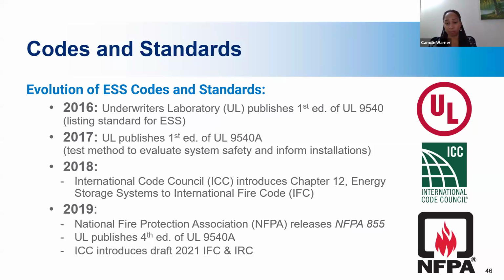It's a certification. In 2017, UL 9540A was developed. This is not a certification, it's a destructive test that provides data to review to make sure you're making informed siting decisions. UL 9540A is not a pass or fail test; it simply tells you how the system will behave under a stressful situation. This is why peer review is crucial, because developers will hand you a very thick 9540A report and say, here's the data, but you need someone that speaks battery energy storage and can understand what that test result is actually saying.